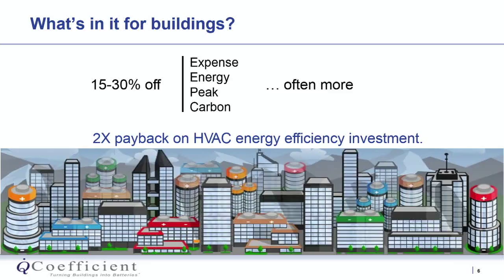We found out that when we optimized a building just around hourly energy prices, as a byproduct we got a 30% peak demand reduction. That should make some sense if you're optimizing around prices—they're highest on the hottest days, middle of the afternoon.